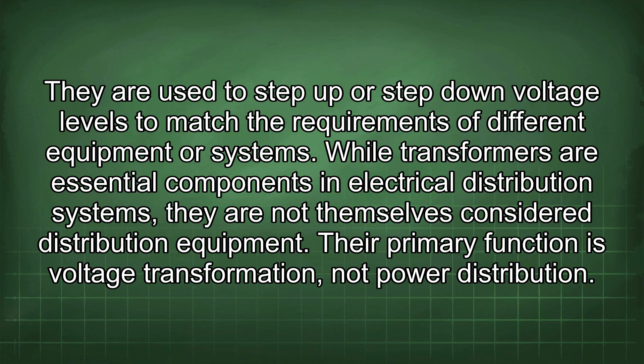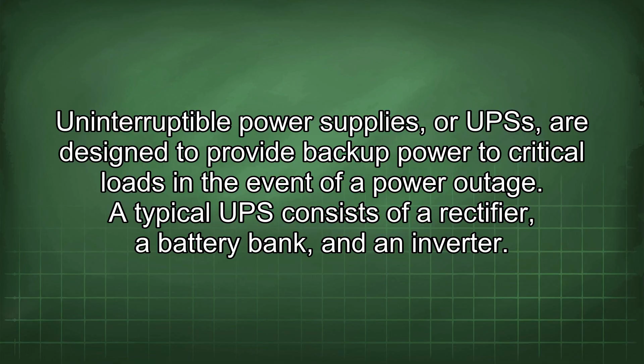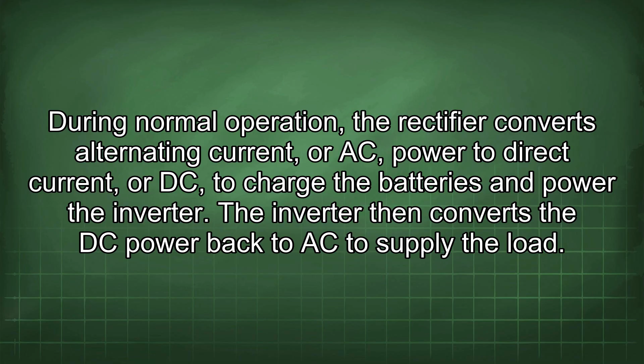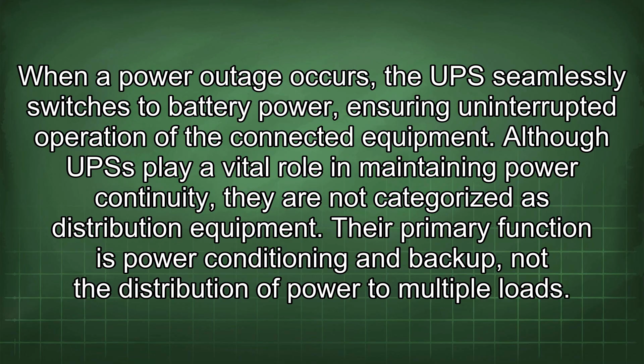Uninterruptible power supplies, or UPSs, are designed to provide backup power to critical loads in the event of a power outage. A typical UPS consists of a rectifier, a battery bank, and an inverter. During normal operation, the rectifier converts alternating current, or AC, power to direct current, or DC, to charge the batteries and power the inverter. The inverter then converts the DC power back to AC to supply the load. When a power outage occurs, the UPS seamlessly switches to battery power, ensuring uninterrupted operation of the connected equipment. Although UPSs play a vital role in maintaining power continuity, they are not categorized as distribution equipment. Their primary function is power conditioning and backup, not the distribution of power to multiple loads.